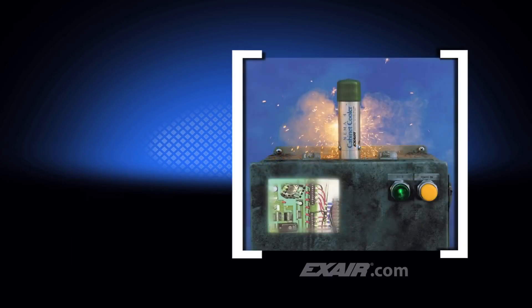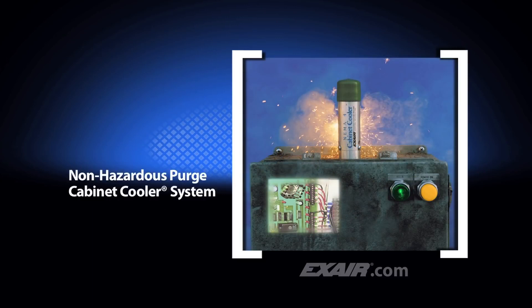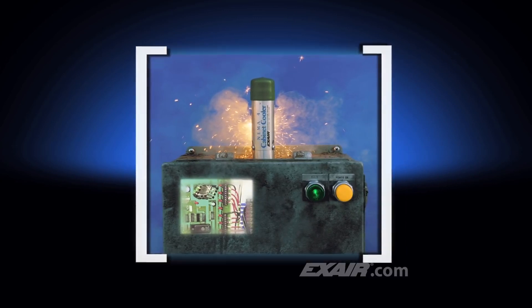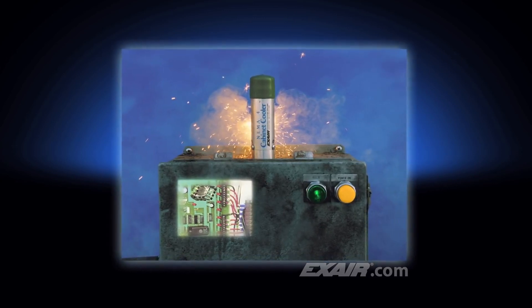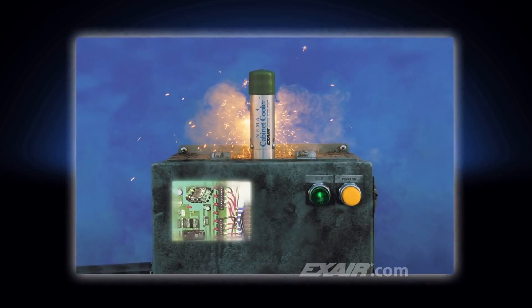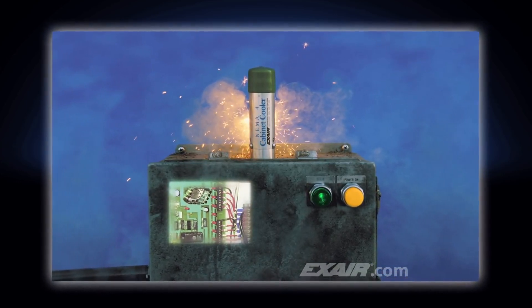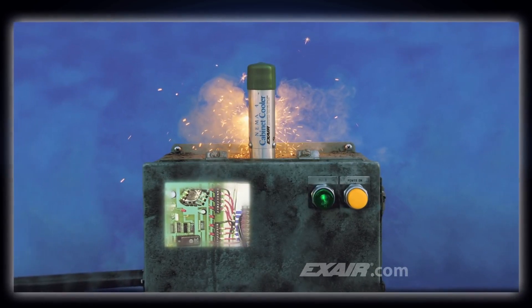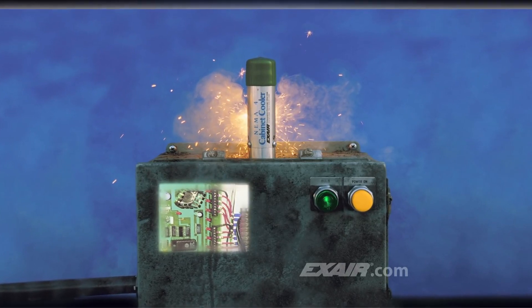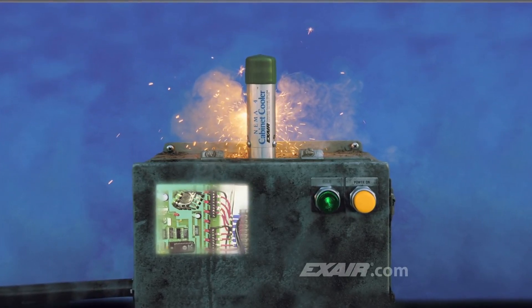EXAIR manufactures special cabinet coolers suited to specific environmental requirements. The non-hazardous purge cabinet cooler systems are ideal for dirty areas where contaminants might normally pass through small holes or conduits. Under normal conditions, the NHP cabinet cooler systems provide a slight positive pressure in the enclosure, passing 1 SCFM or 28 SLPM of air through the cooler when the solenoid valve is in the closed position. When the thermostat detects high temperature, it energizes the solenoid valve to pass full line pressure to the cabinet cooler, giving it its full cooling capability.